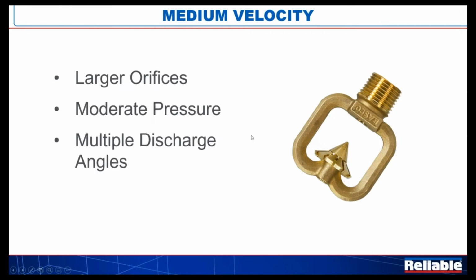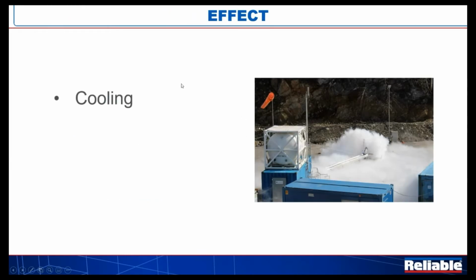You have to look carefully, but when you look at these nozzles, you'll see that those deflector tines start to flatten out or steepen, and that's the mechanism by which we shape that cone. And then finally, again, the internal deflector. So why do we use a deflector on a sprinkler to begin with? The same reason we use it on the medium velocity nozzles: to break the water into the appropriate water drop size. It shapes and breaks the water into much finer particles than it does for the high velocity. So what effect are we having on the fire?